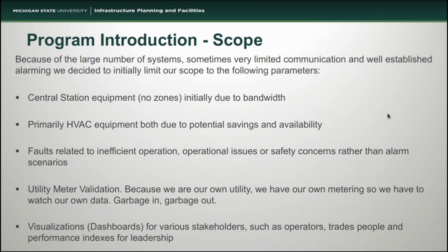Because we had this large control room with people that are watching the alarms and the more emergency scenarios, we decided rather than trying to duplicate that, we wanted to look for faults that were related to inefficient operation, operational issues, or things that could be safety concerns. And these range from lab pressurization to inappropriate set points, or control systems that just aren't controlling the way that we intended them to due to changes over time.